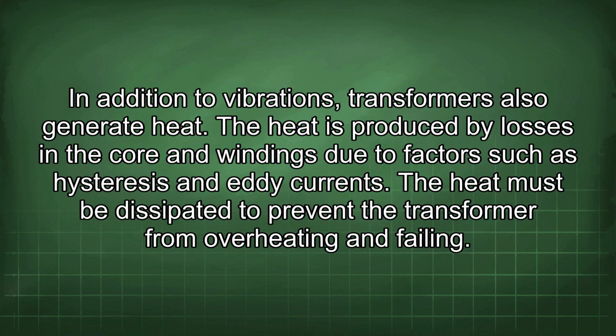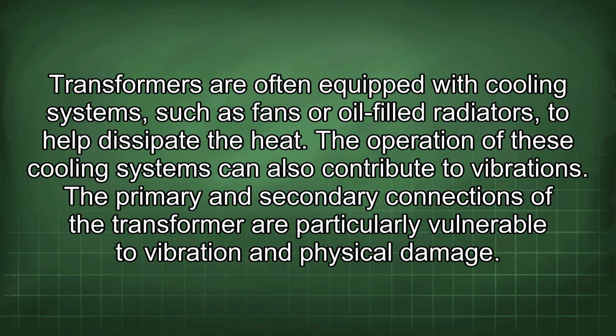In addition to vibrations, transformers also generate heat. The heat is produced by losses in the core and windings due to factors such as hysteresis and eddy currents. The heat must be dissipated to prevent the transformer from overheating and failing. Transformers are often equipped with cooling systems, such as fans or oil-filled radiators, to help dissipate the heat. The operation of these cooling systems can also contribute to vibrations.